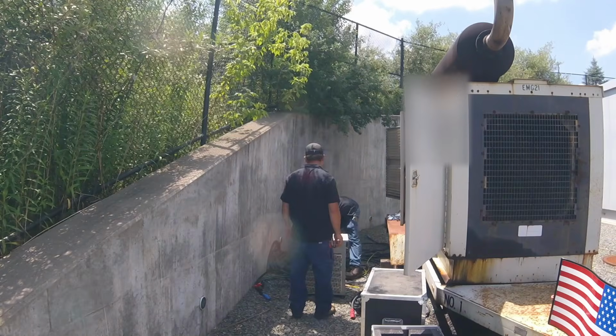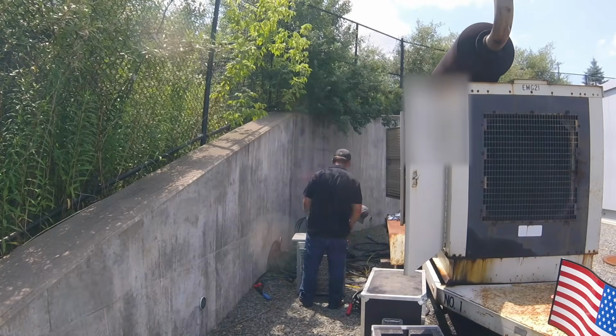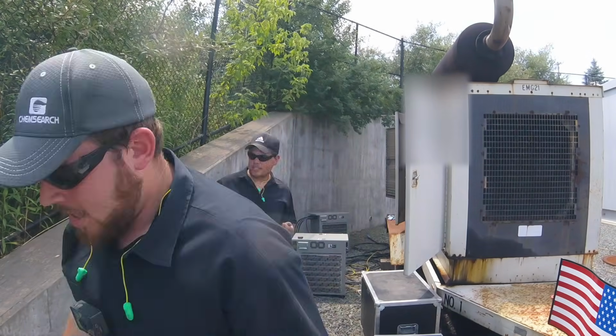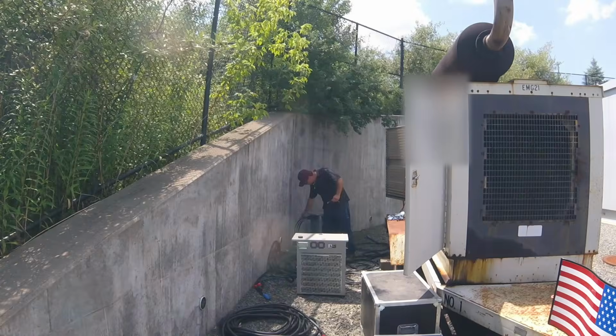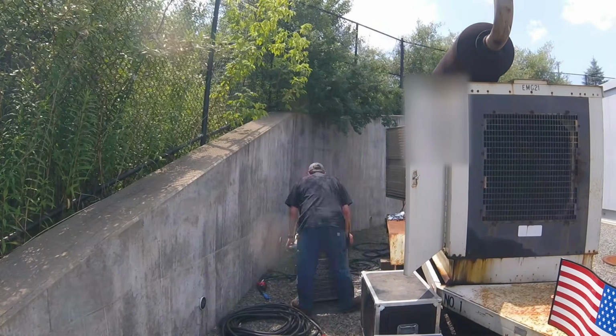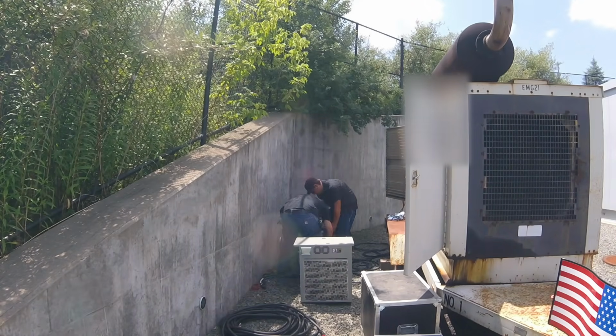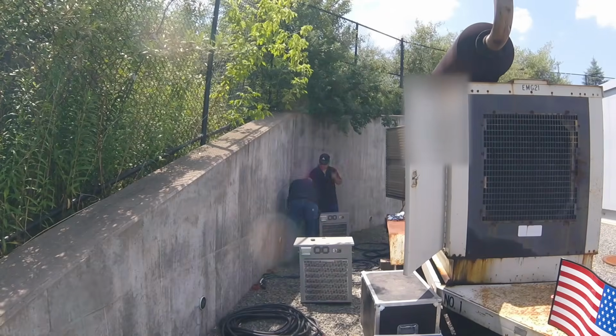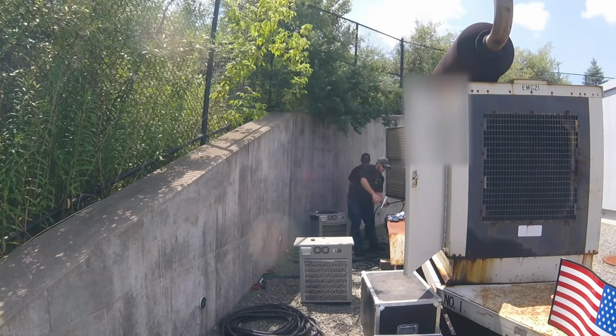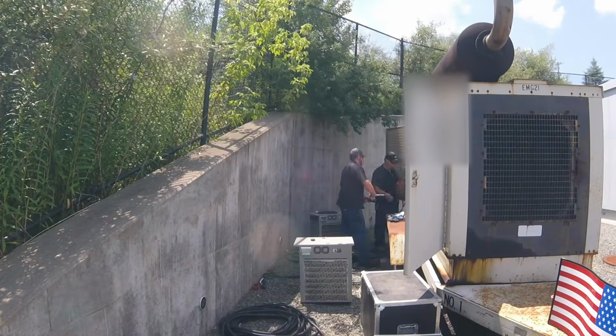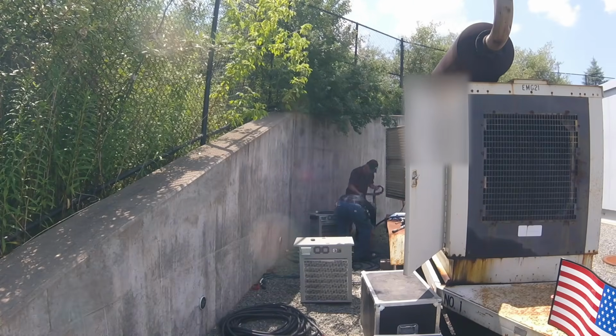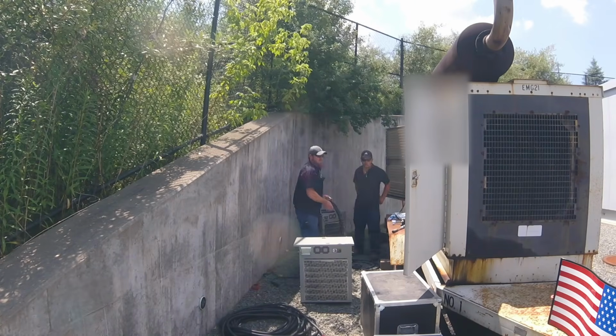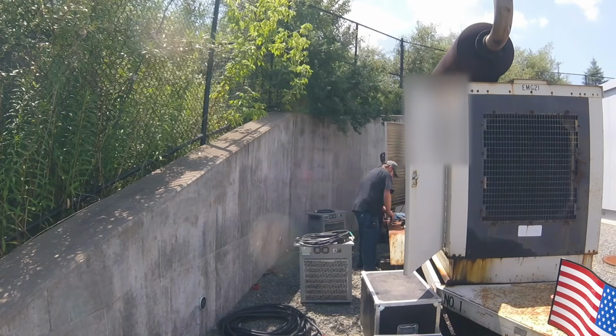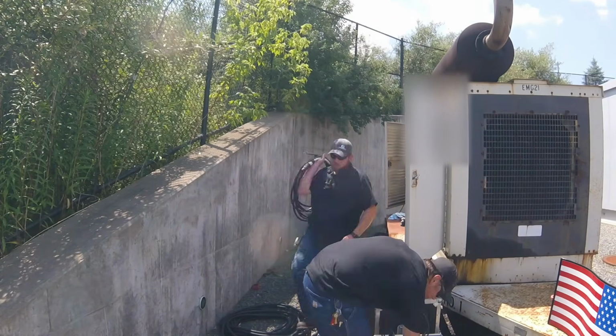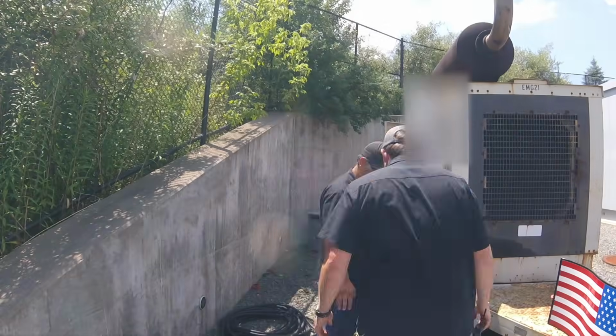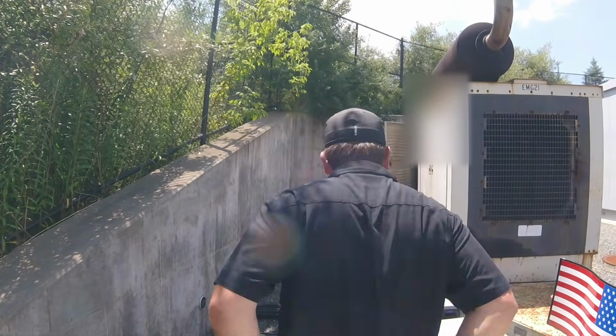So that's going to be it for this video. We were able to get this old Cummins fired up. I had faith in it, you know, it always fires right up. Sometimes you need 4 jump packs and jumper cables from the truck, but it always fires up. We also determined that the breaker is indeed good. Voltage is a little low, so we're going to have to look into that, see if we can adjust the voltage regulator. So we're guessing whatever they had hooked into it, maybe they had something crossed, so every time they tried to power it up it would short, which is weird because it was running fine. They were using it for probably a week before they started having issues with it. Maybe they were just sick of how noisy it was, so they just created a crisis.